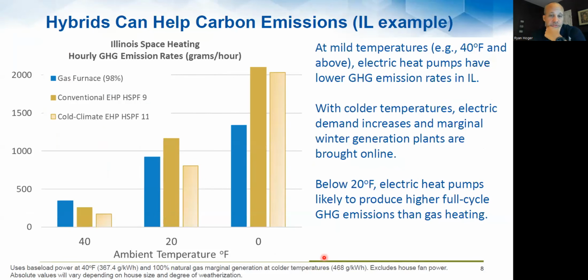I like this one a lot, and I use this one with all the HVAC guys when I'm trying to convince them to do dual fuel systems. This is 3 examples at 0, 20, and 40 degrees outdoor air temperature. And this is emission rates, right? So basically we're trying to figure out how much greenhouse gas emissions we're putting into the air. As you probably all are well aware, a lot of that comes from combustion processes, which put carbon into the air. It also comes from refrigerant leaks and other kinds of chemicals that people do stuff with. But in this case, it's specifically coming from the combustion process.